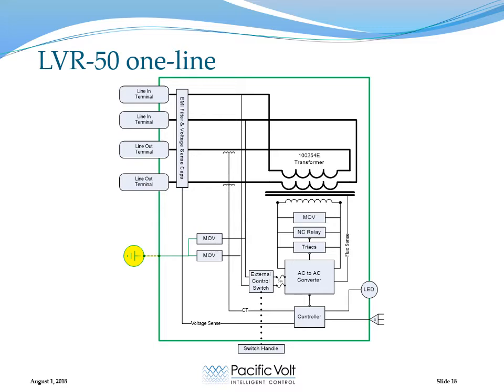This is a one-line diagram of the LVR50. The core of the technology is the AC to AC converter, which in conjunction with the control board controls the voltage and polarity across this control winding, and that provides the sub-cycle regulation. So as we impress a voltage on this winding, it is reflected onto the secondary, and it either adds or subtracts voltage to each of the two hot phases coming in, which pass directly through these windings and out. So the regulator can be bypassed with the external switch here, which shorts this winding out and lets the regulator continue to supply power to the customer, but there's just no regulation.